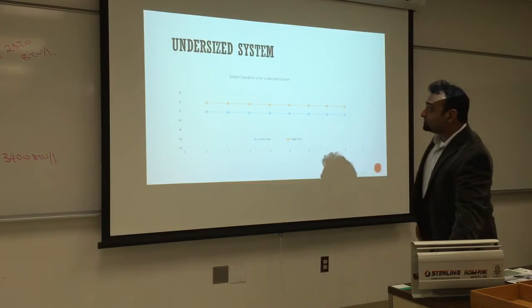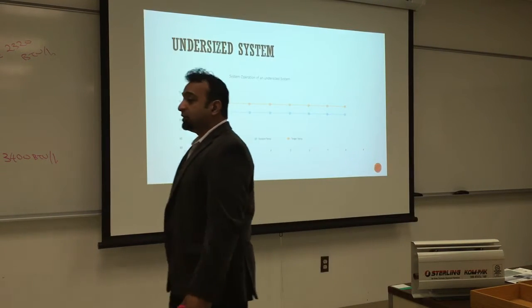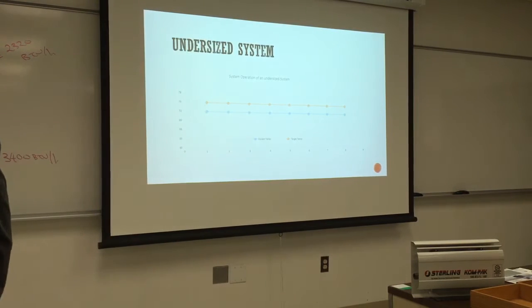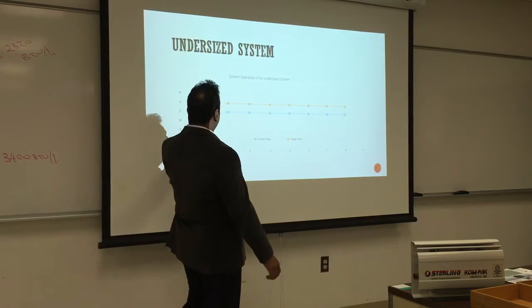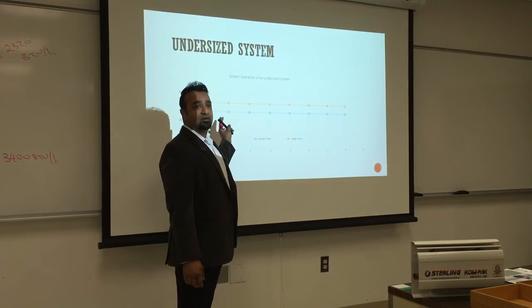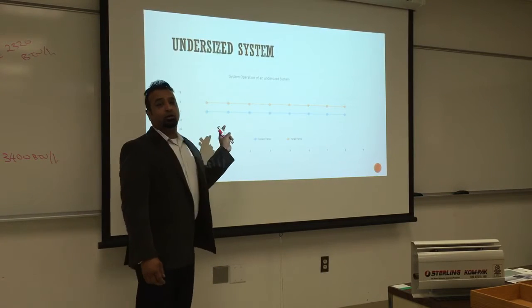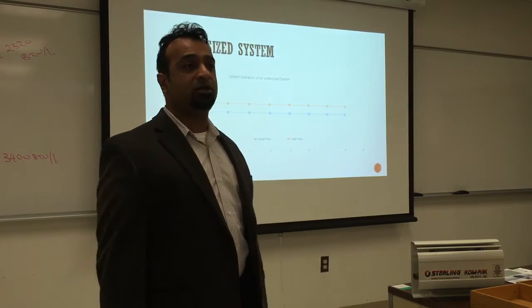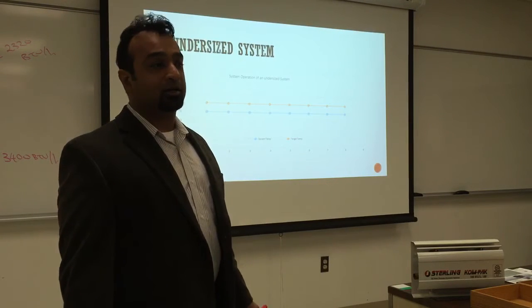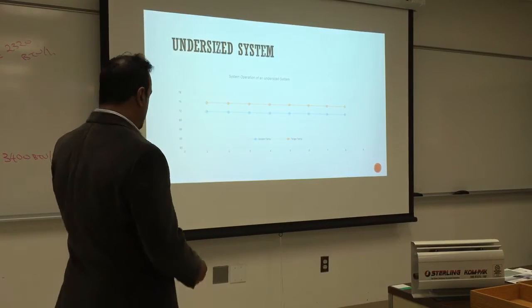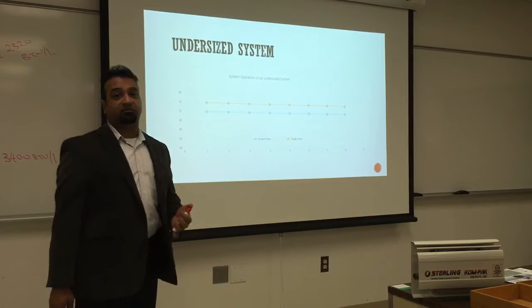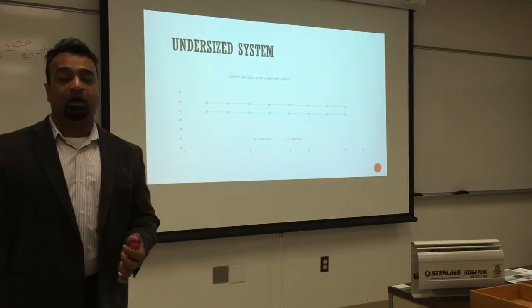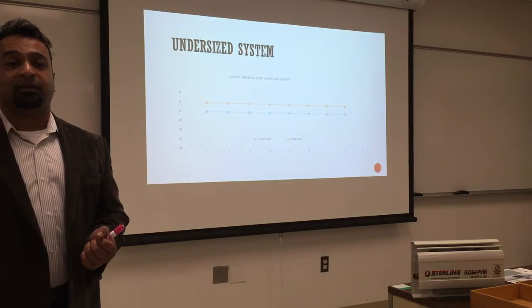If the system is undersized and it's really cold outside or you're activating all the zones, it probably won't keep up. It will be on all the time but never reach the target temperature. It ends up overworking, the system may overheat, you're uncomfortable, and at some point the system might fail. You can run it for a while, but you'll never reach the correct temperature.